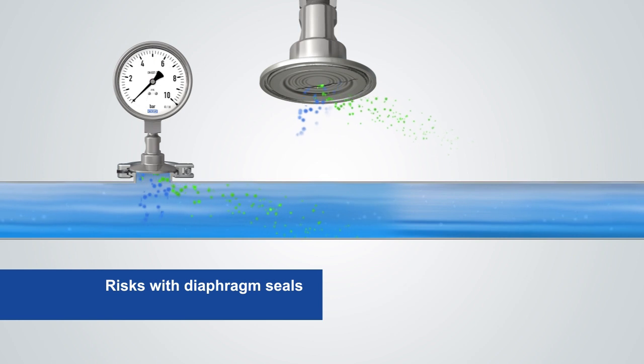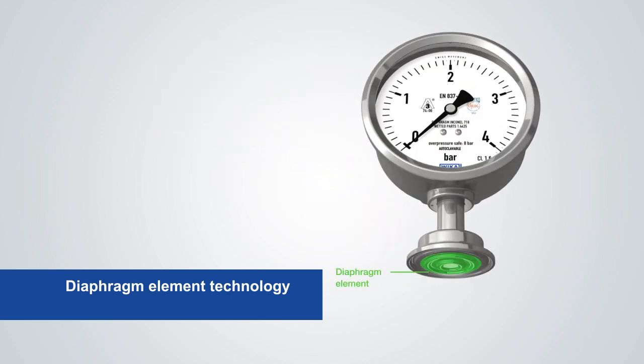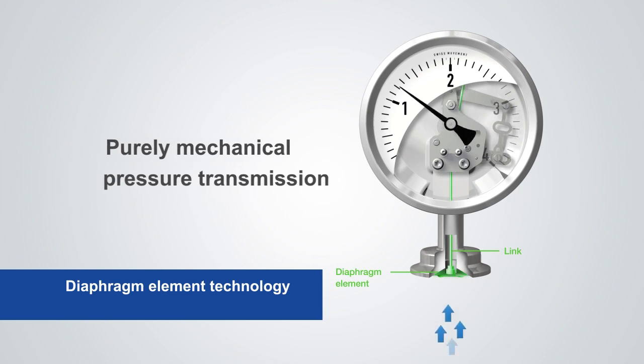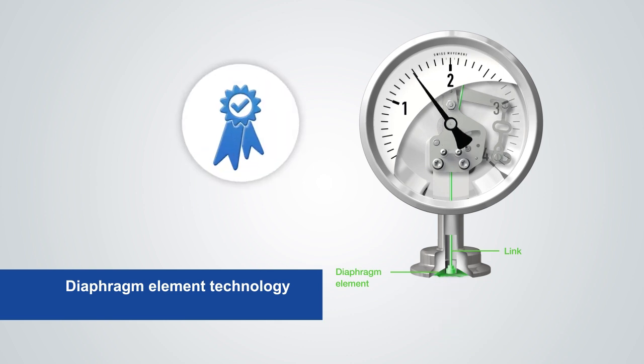Such a diaphragm rupture can be detected immediately with special WIKA measuring instruments, either using a diaphragm seal which includes diaphragm monitoring or a diaphragm pressure measuring instrument. With diaphragm pressure gauges, the pressure is transmitted from the diaphragm element to the display purely mechanically, without any system fill fluid. In this way, the dry measuring cell increases process safety.